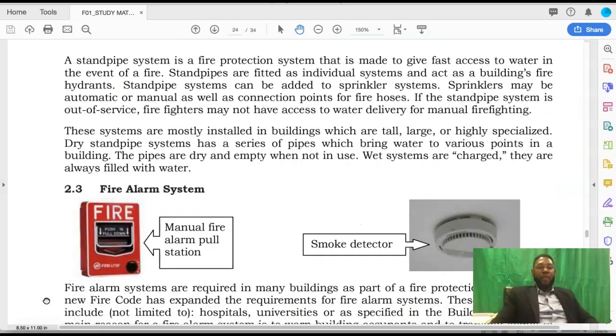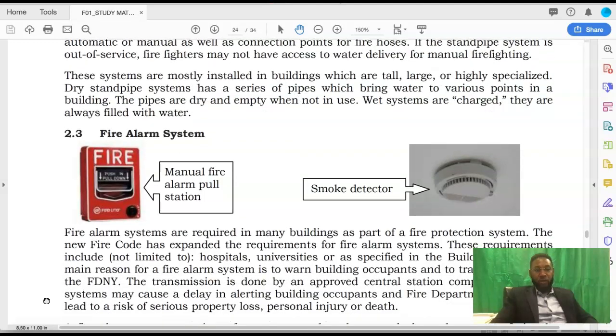Standpipes. A standpipe system is a fire protection system that is made to give fast access to water in the event of a fire. A standpipe is like a mini fire extinguisher attached to a building. Okay, it's not a public one, it's attached to the building. So standpipes are fitted as individual systems and act as a building fire hydrant. Standpipe systems can be added to sprinkler systems. They may be automatic or manual, as well as connection points for fire hose. If the standpipe system is out of service, firefighters may not have access to water delivery for manual firefighting. So that's serious.